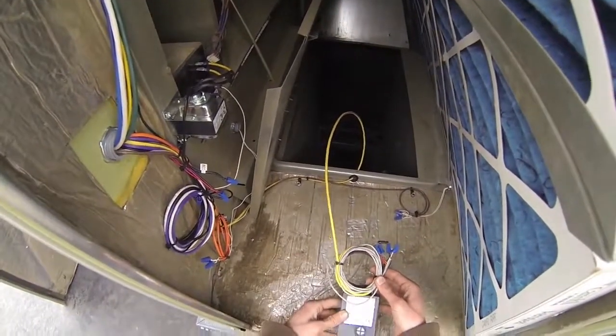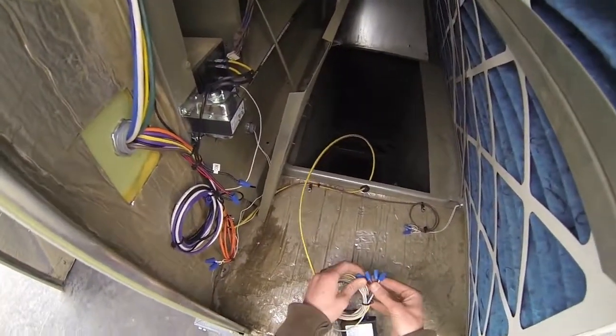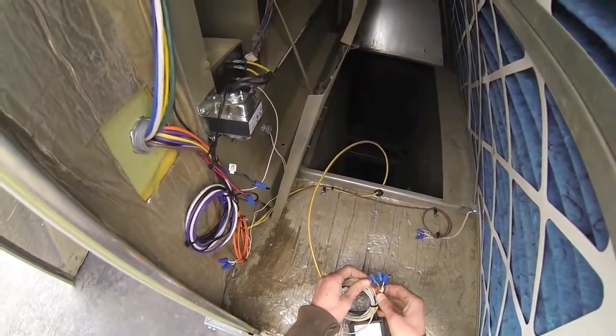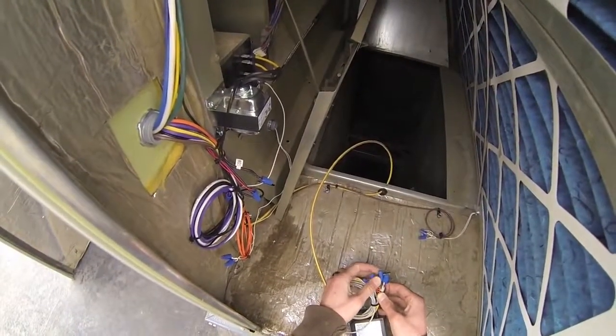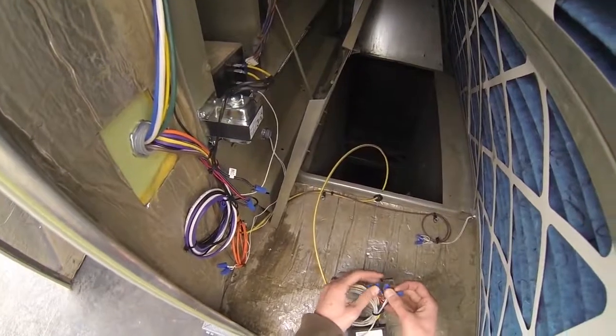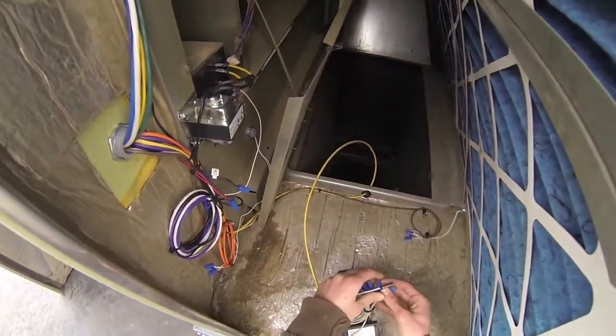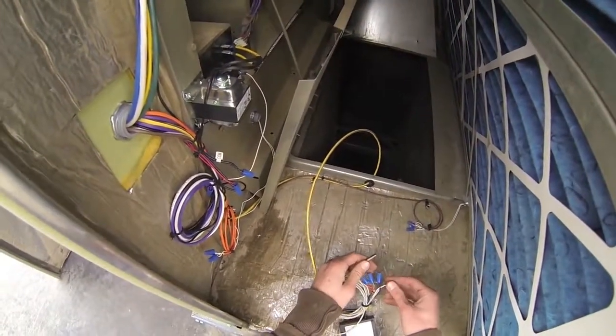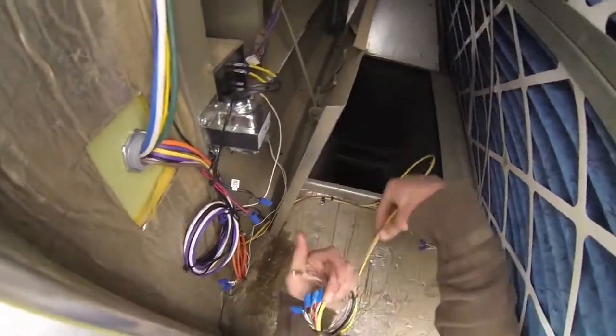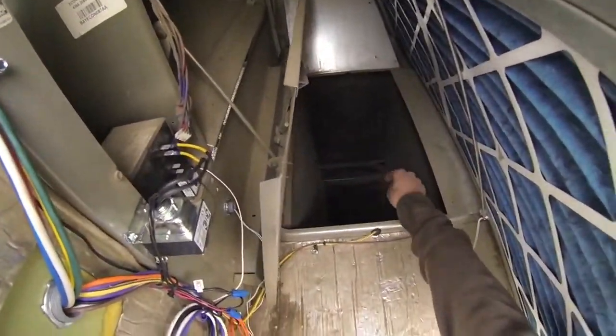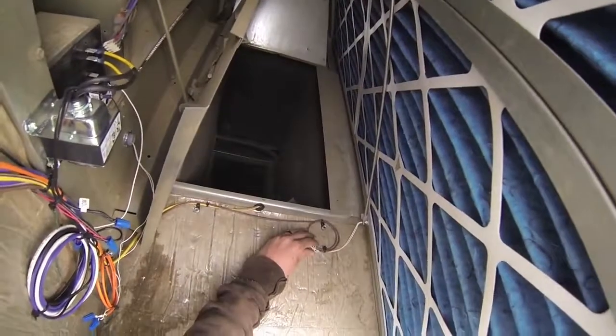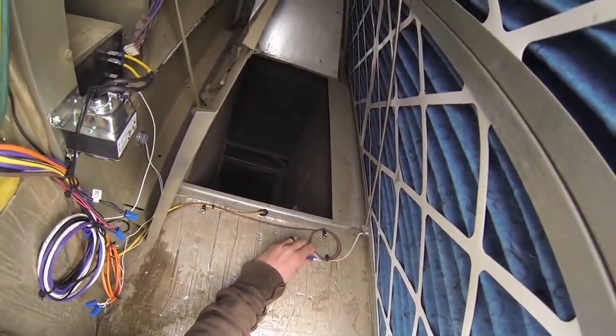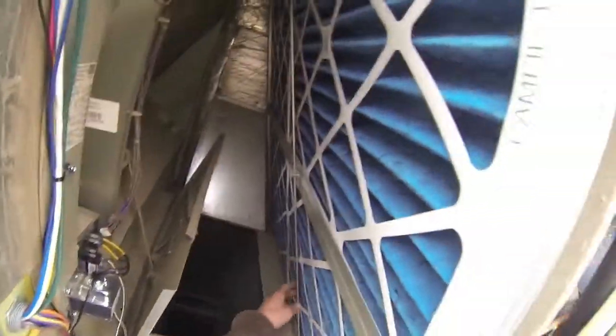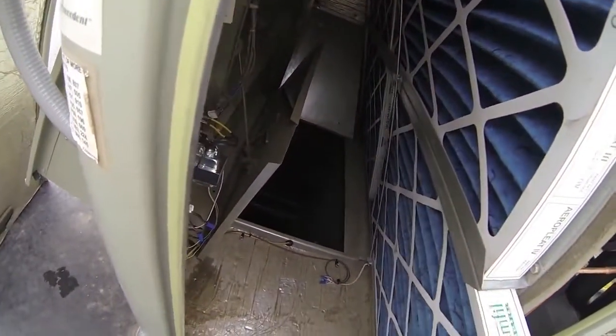Return sensor and CO2. For that we have our CO2 wired up red to red, brown to green, black to black, and the black from our sensor is also in there, so the 3 blacks go together, and the red from our sensor with the white, and that just hangs inside the return. Then we have our mixed air sensor, the brown 2 conductor, which we secure along the rack, making sure we still allow the filters to be retrieved.